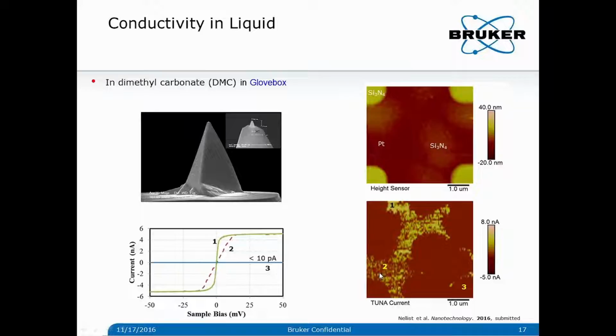We can use point and shoot to capture the IV curve at the locations we're interested in. The IV curves captured around these three locations, numbers 1, 2, and 3, are shown on the left. As you can see, number 1 is the most conductive, number 2 is less conductive, and number 3 is on the silicon nitride island, where we would not expect any meaningful current. That is true: the IV curve only shows about 5 picoamps of background current.